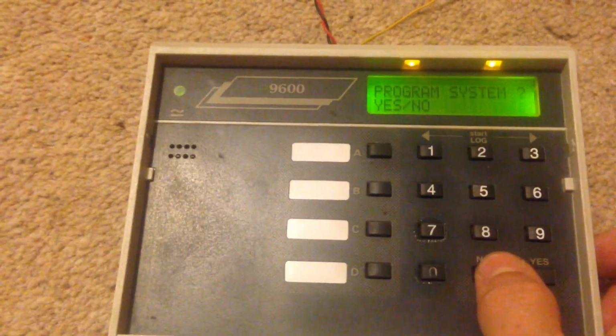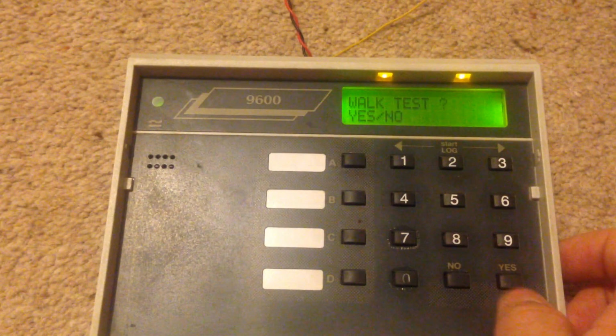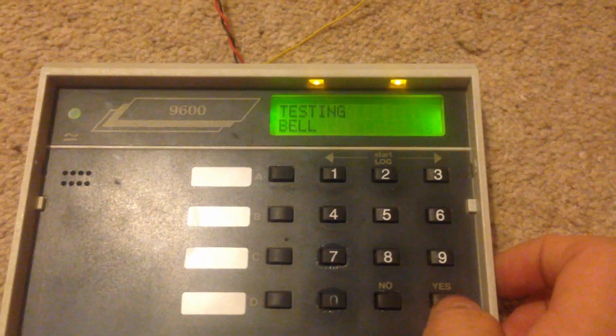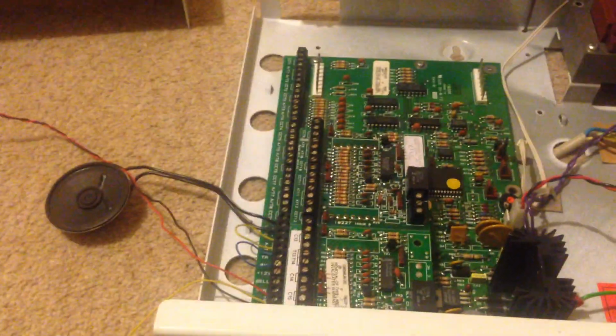Load defaults. Well, we could do that if we wanted to. We don't want to reset the system. We don't want to program it. Let's test the bells. So there's that. Then there's the bell, which energizes the bell outputs there where TR is, but it also activates that relay, which is standard on the 9610. Then the strobe is going to be this output here, and then we're testing the keypad sounders.